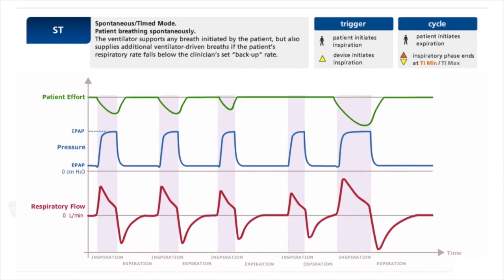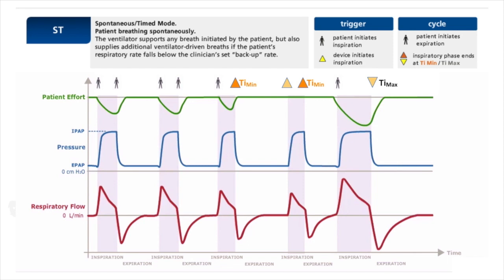ST mode is Spontaneous-Timed mode. The patient breathes spontaneously and the ventilator supports any patient-initiated breath. However, if the patient fails to meet the set backup rate, the device can initiate inspiration. Regarding cycling: the patient can cycle to exhalation; TI min prevents premature exhalation; and if the patient fails to initiate exhalation, cycling occurs at TI max. Viewers may pause to review the graphical details.